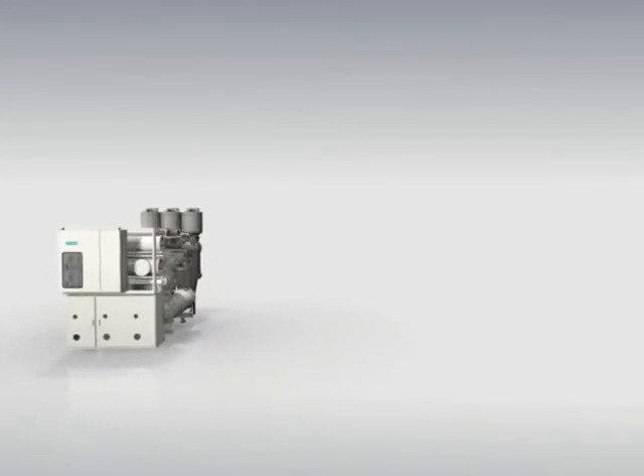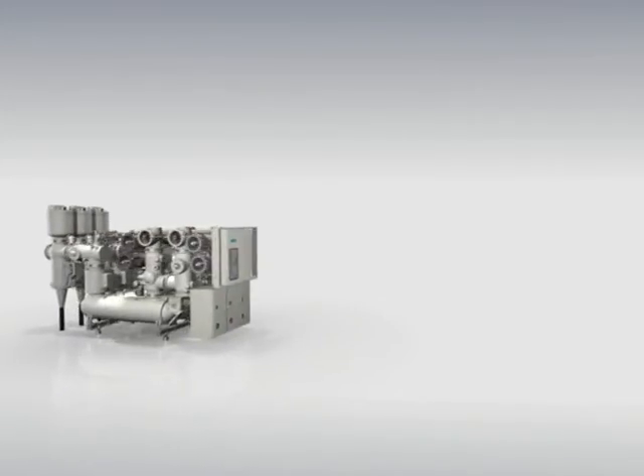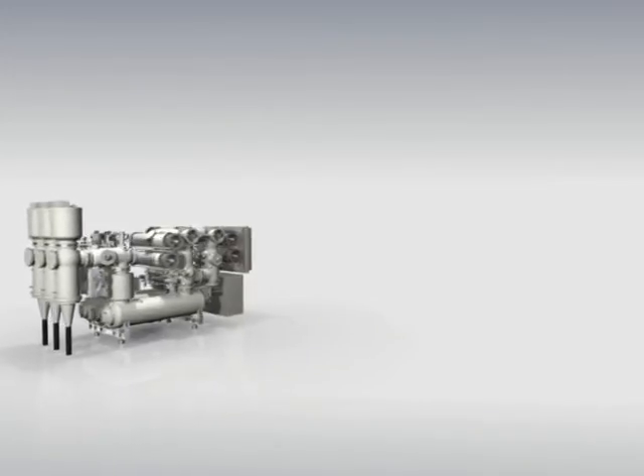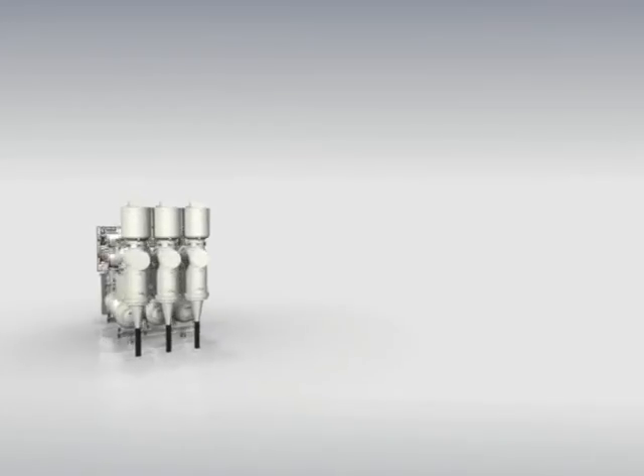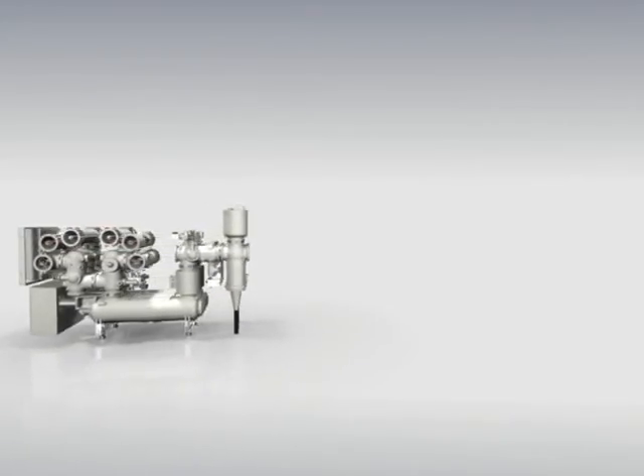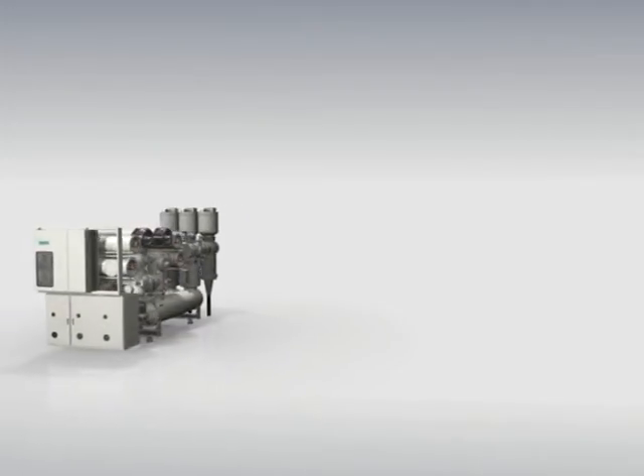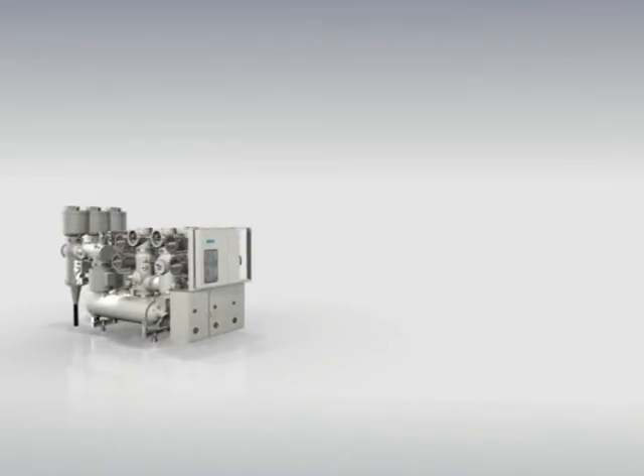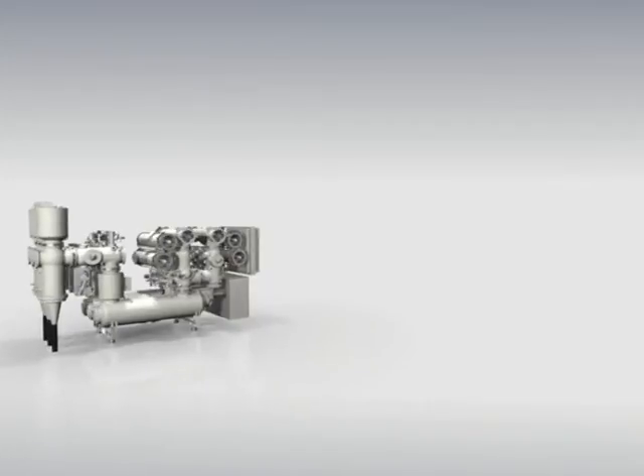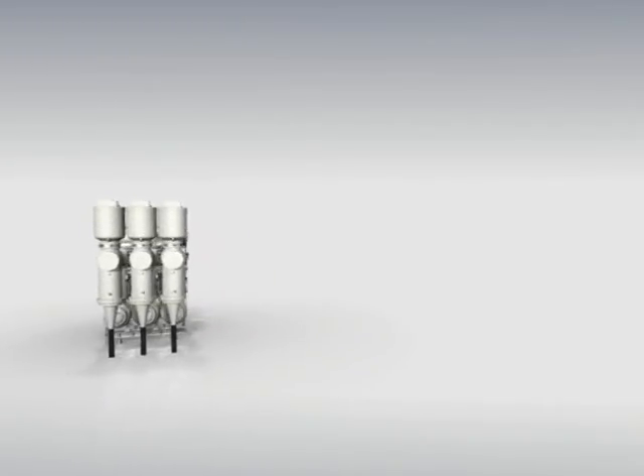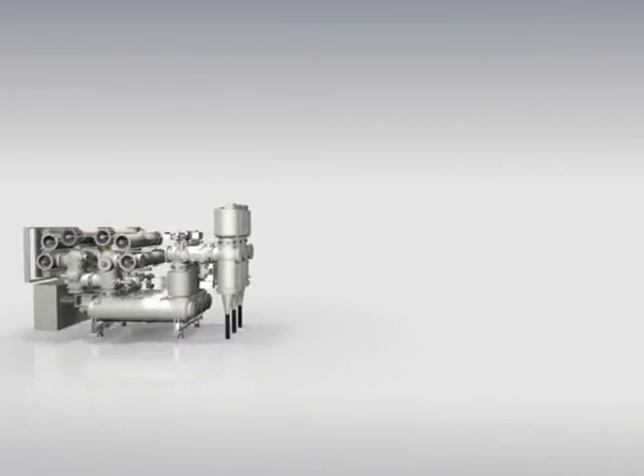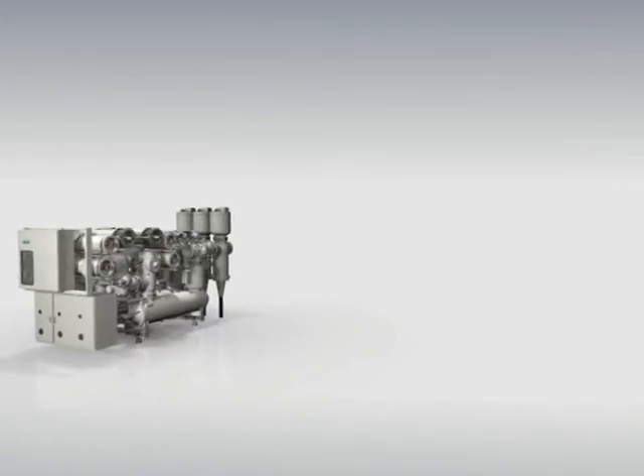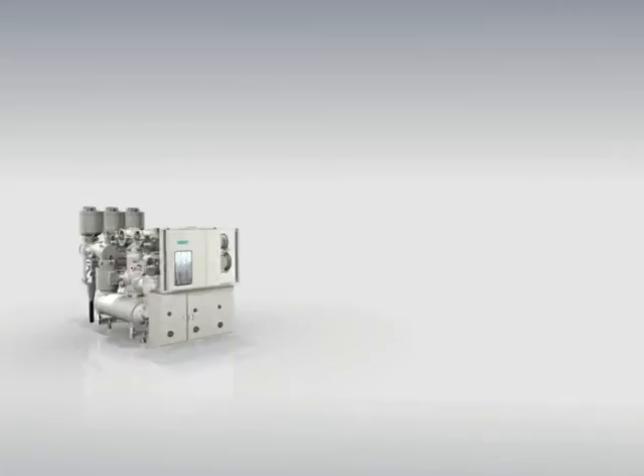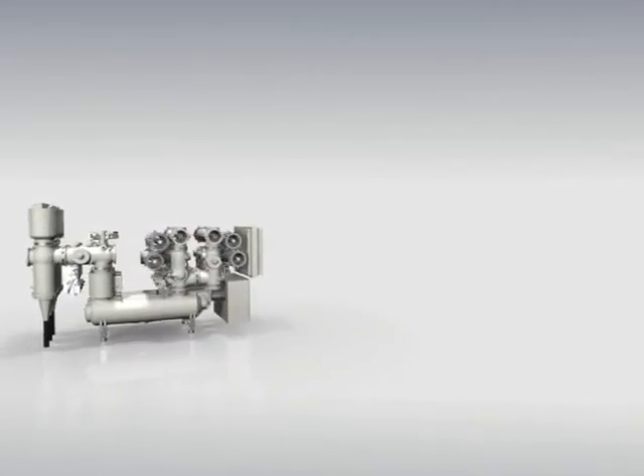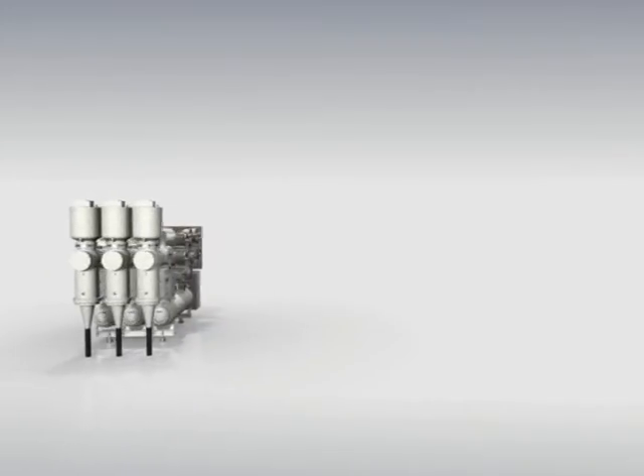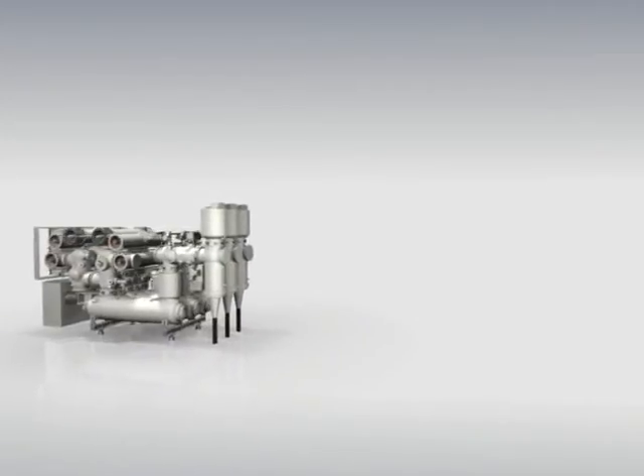its high reliability and availability, outstanding operating safety, its extremely durable and virtually maintenance-free passive busbar, the possibility to exchange the circuit breaker module during operation of the switchgear, its corrosion-proof aluminum enclosures, its high degree of operating safety thanks to a seamless enclosure surface and high dielectric safety, short erection and commissioning time due to complete pre-assembled and pre-tested bays, its high degree of gas tightness, which provides for environmental friendliness, almost negligible maintenance, its long service life, low life cycle costs, type approval and certifications to the latest IEC and IEEE standards.